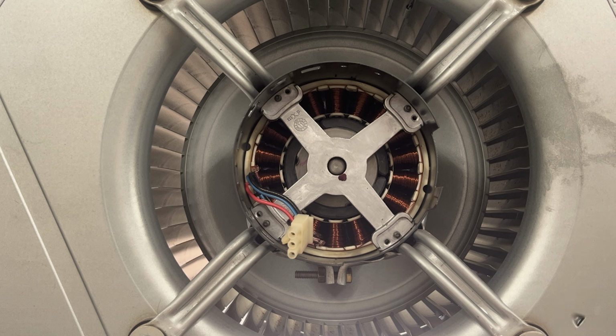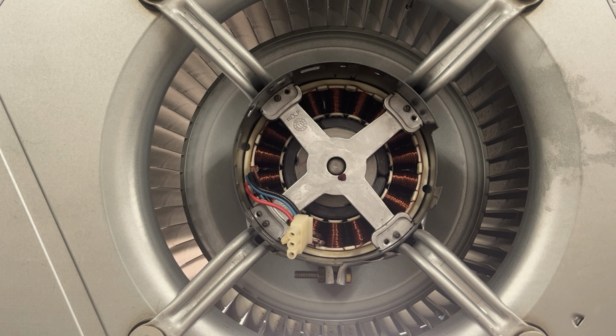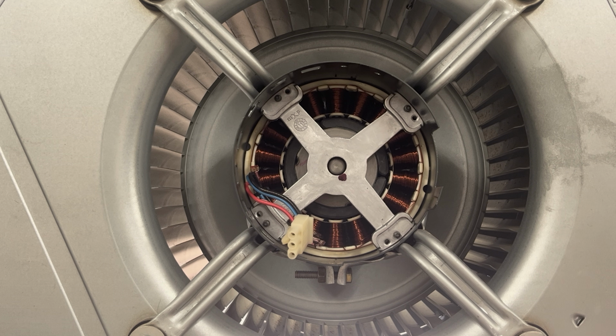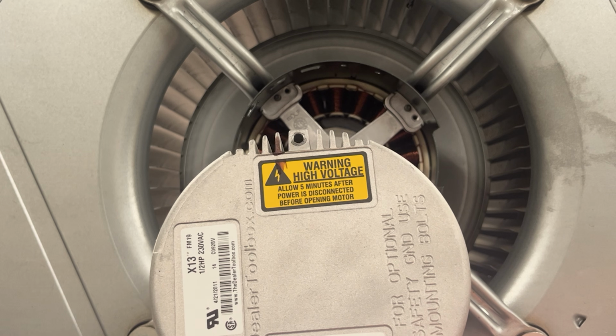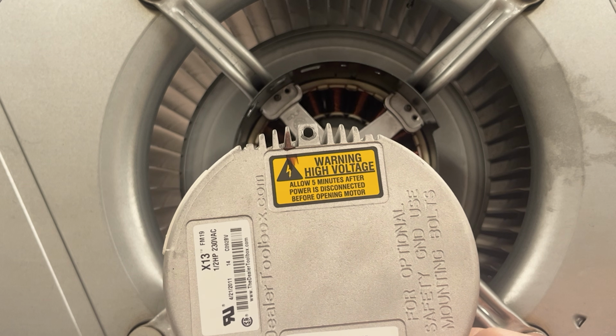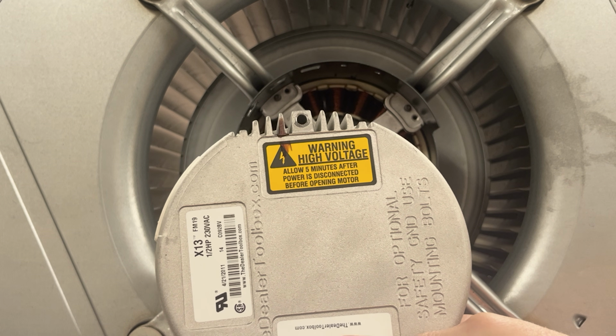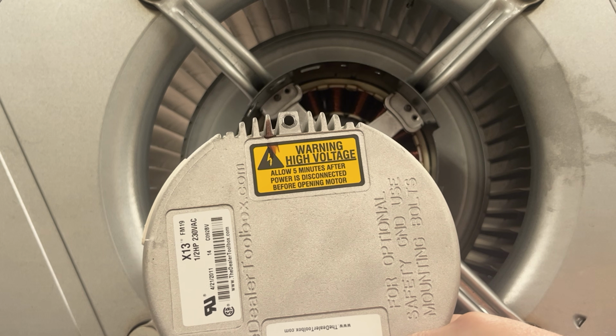Sometimes these motors, once you get them going, they don't like it when they shut off when they have problems. So that's just another perspective to show you out in the field how to test out the motor from the module. Didn't require any voltage there. However, I did have to wait 5 minutes. As you can see here on the warning, it says allow 5 minutes after power is disconnected. They're talking about the 230 volts because there's stored energy on these capacitors.